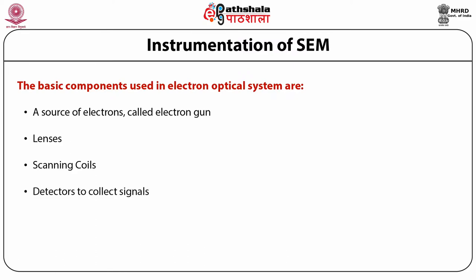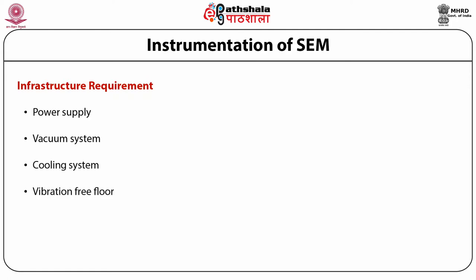The basic components used in the electron optical system are: number 1, a source of electrons called the electron gun; number 2, lenses; number 3, scanning coils; detectors to collect the signals; sample stage; and display or data output devices. The infrastructure requirements are: power supply, a vacuum system, cooling system, vibration-free floor, and a room free of ambient electrical and magnetic fields.